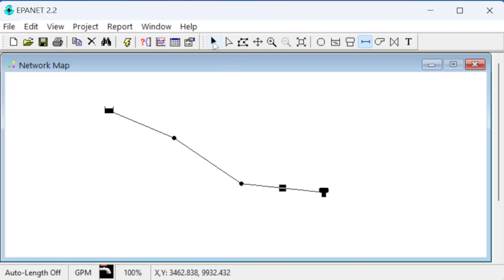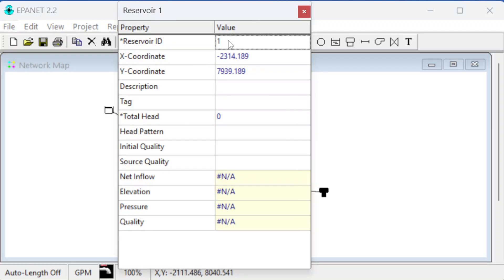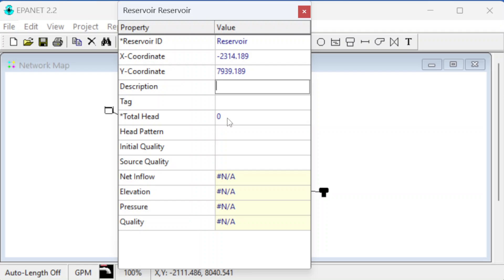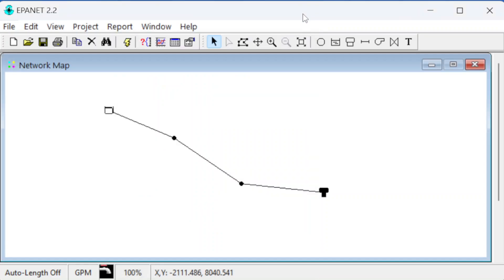Now let's go to the select tool and provide information on these elements. First, the reservoir — we can change its ID to 'Reservoir.' A reservoir is just an infinite source where the water level is fixed. For this one we set the total head at 100 feet — units are feet when working in gallons per minute and US units.